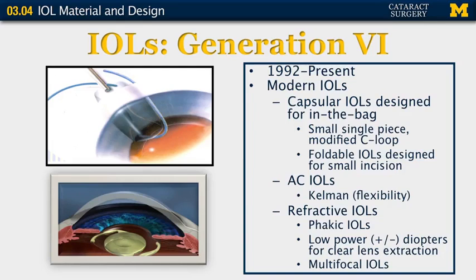Finally, we get up into the sixth generation, or what are considered the modern currently in-use lenses. These were first developed and introduced around 1992, and these lenses are designed for placement into the capsular bag. We have small single-piece lenses and lenses with three-piece design, meaning that the haptic and the optic are made of different materials. These lenses can now be foldable and placed through smaller incisions into the capsular bag. We're still using the Kelman very flexible open haptic anterior chamber lenses, which are still in widespread use when indicated. And we also have different options with refractive lens implants available.